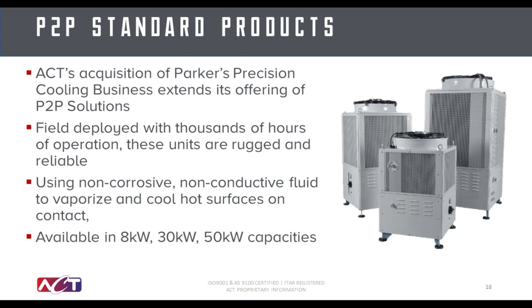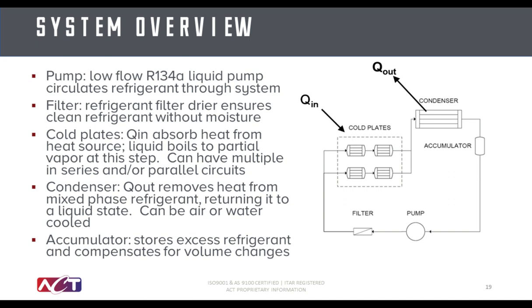The product offerings include options for 8 kilowatts, 30 kilowatts, and 50 kilowatts, as you can see in the image on the right. Inside of each of these components is a pump, a filter, multiple cold plates, a condenser, and an accumulator. The filter dryer is used to eliminate any unwanted moisture in the system, as well as filter out any components that may have been generated. The system includes dry break quick disconnects so that the cold plates can be easily swapped if a diode ever needs to be replaced.